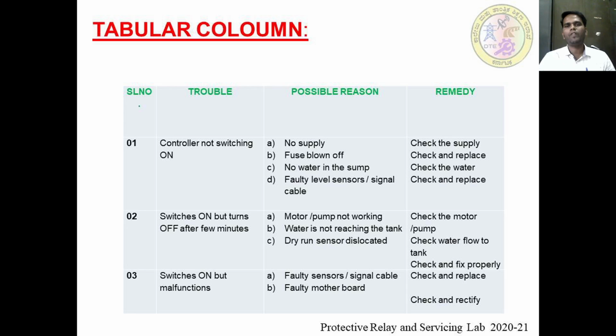So the remedy for this is to check the supply, whether it is coming to the controller or not; if not, check and replace it. Next, check the water level in the sump, whether water is filled in the sump or not; if not, fill the water in the sump.